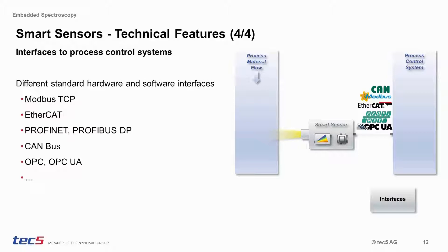Whether using a univariate or multivariate approach, our smart sensor device is capable of constantly providing the concentration of a specific ingredient in the product matrix. Our smart sensor platform offers a wide range of hardware and software interfaces for the onward transfer of such data to a PLC for further control and monitoring. Standard protocols like Modbus TCP, Profibus DP, OPC UA, and many more are supported. Our smart sensor devices not only transmit fully prepared analysis results in real-time — additional relevant sensor status information is also made available to a process control system or even to a cloud-based network.